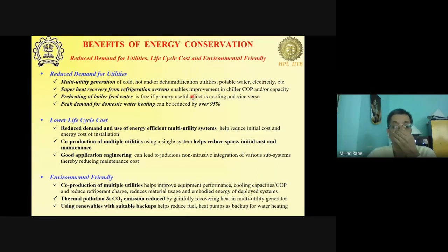single unit. Superheat recovery from refrigeration systems can not only give you free hot water, it can also improve the performance of the refrigeration unit in terms of improved cooling capacity and COP. Preheating of boiler feed water can be considered to be free if air conditioning is the primary demand. And peak demand for domestic heating can be reduced by over 95%.